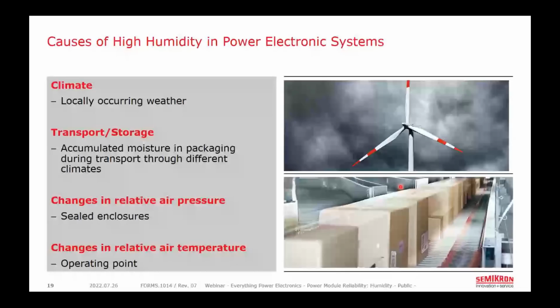Air pressure also plays a role in the temperature and humidity on a large scale in the macro environment. Usually this is not considered unless you have a highly sealed enclosure that is designed to prevent water or gas ingress. And as we discussed earlier, relative humidity can change with air temperature. So the biggest issue is changes in and around the power semiconductor modules. And that's what we're going to focus on here, the stuff immediately around the power semiconductor module.